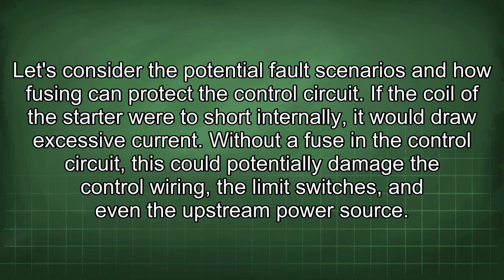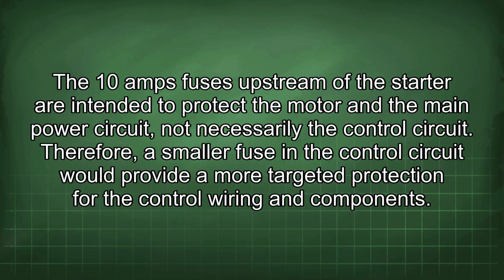Let's consider the potential fault scenarios and how fusing can protect the control circuit. If the coil of the starter were to short internally, it would draw excessive current. Without a fuse in the control circuit, this could potentially damage the control wiring, the limit switches, and even the upstream power source. The 10 amp fuses upstream of the starter are intended to protect the motor and the main power circuit, not necessarily the control circuit. Therefore, a smaller fuse in the control circuit would provide a more targeted protection for the control wiring and components.